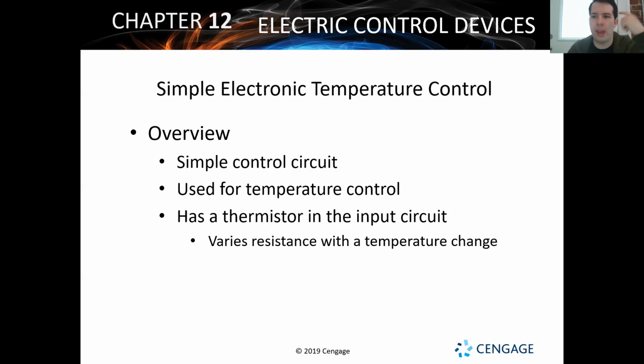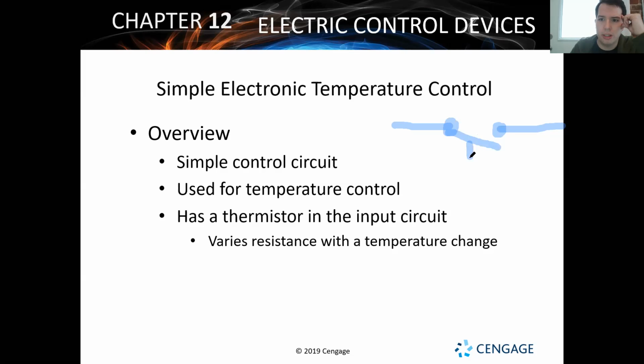So how a typical switch is going to be working. Let me see if I can get this to come up easily. All right, so you'll have it where you've got a switch - we're talking about a temperature switch. This right here, what I'm drawing, is temperature closing on a rise - that's a normally opened switch. And this is a normally closed switch for temperature on the rise.